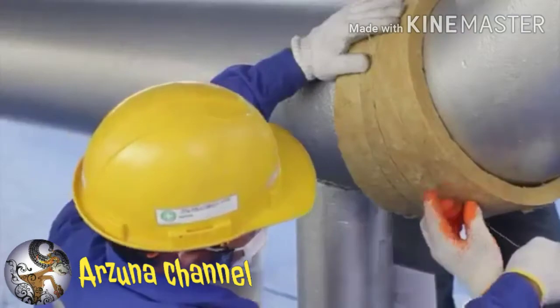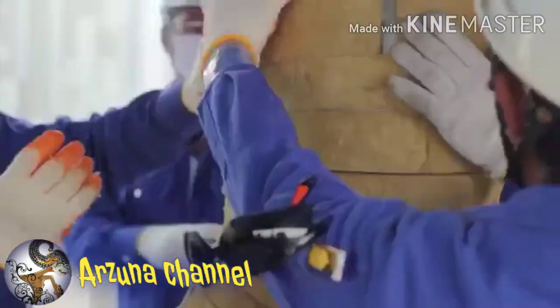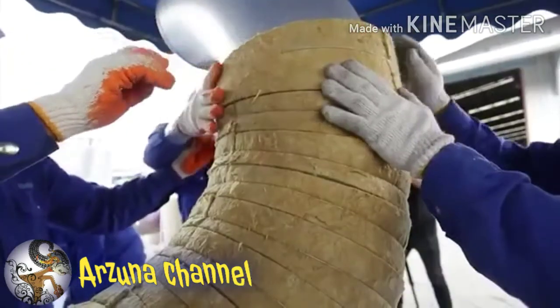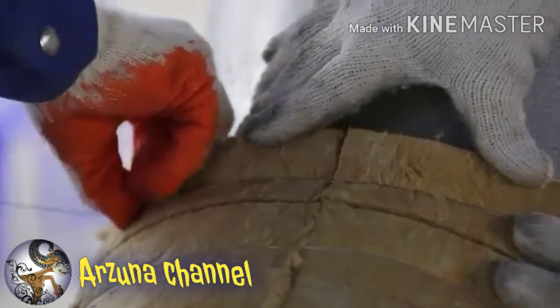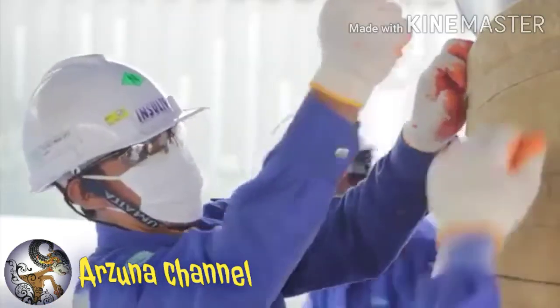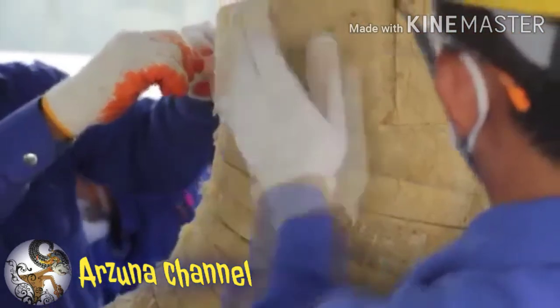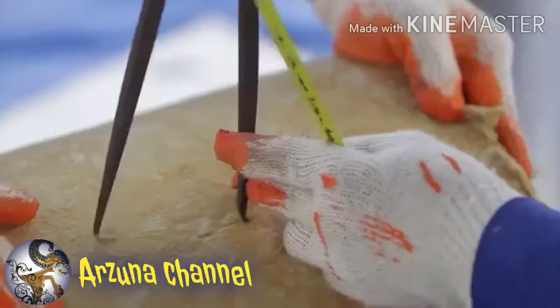The curved surfaces of pipe should be insulated with prefabricated insulation, which is fabricated according to the curve or elbow characteristics, from the bottom to top, one by one. The pipe section should be fabricated with proper tools. The fabricated insulation should be secured with galvanized binding wire or with steel bands. Then, the sharp leftover wire can be kept inside the Rockwool Pro-Rox pipe section for safety purposes.